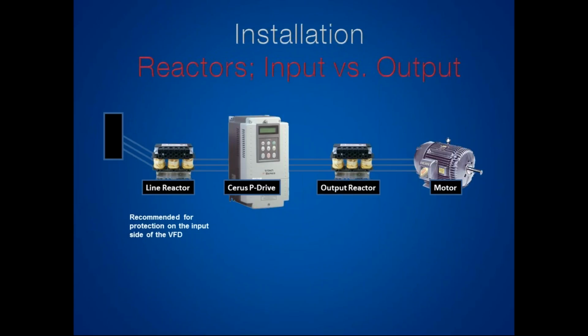So speaking of line reactors, let's talk a little bit about line reactors and what you can expect. The reason we include line reactors is because of harmonics. Drives generate harmonics, okay? Harmonics generate extra heat. They can cause equipment to malfunction. Harmonics in and of itself are its own 30-minute webinar, so I'm not going to delve into harmonics too much. But basically, drives generate harmonics, and if we're going to use drives or any other nonlinear equipment, the engineering community says that we have to meet a standard called IEEE 519. IEEE 519 is basically saying that we're doing something to help mitigate those harmonics created by our drive, okay?